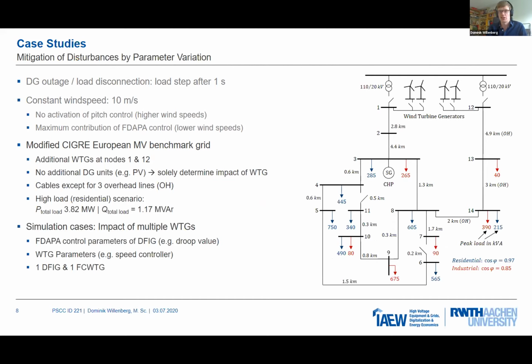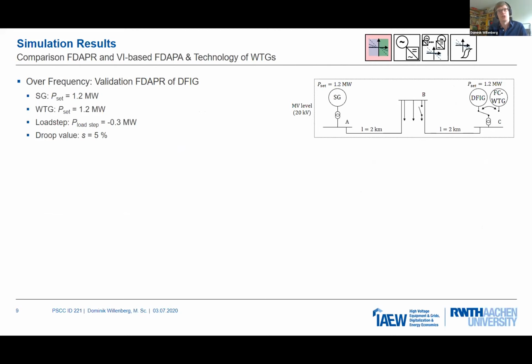For the simulation cases, parameters such as the control parameters for the different FDAPA approaches are changed. In general, just wind turbine generator parameters are changed, and also differences in the topology are simulated. If we start with the simulation results, we have here an over-frequency situation. This is done to validate the FDAPR of, in that case, the DFIG.